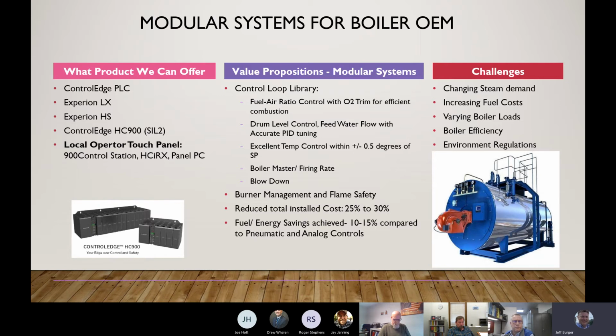control in the HC900. It also does the drum level control, feed water flow, and does this with very accurate PID. It's excellent temperature control, usually within plus or minus 0.5 degrees of set point, which is very tight control, and also offers boiler master and firing rate control. On all of these boilers, since the HC900 does have the SIL2 rating, you can do all the burner management through the HC900, reducing components that you might have to have in the panel, and doing all this under a safe SIL2 rated single platform, the HC900. In the past, to do this type of burner management control, you would have your PID loop controller, and then you would have a flame relay or a flame safety burner management system as a separate entity. In the HC900, you can do all that in one.